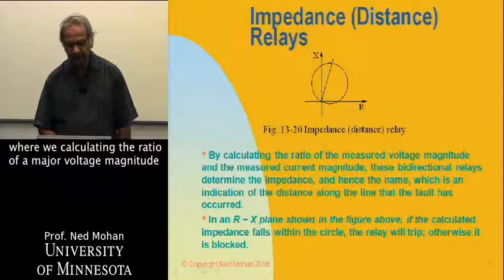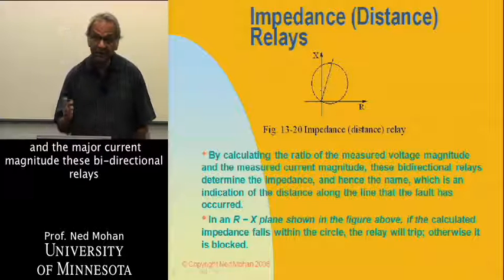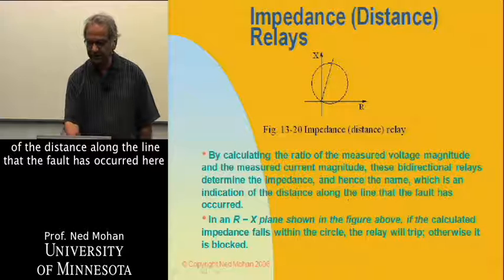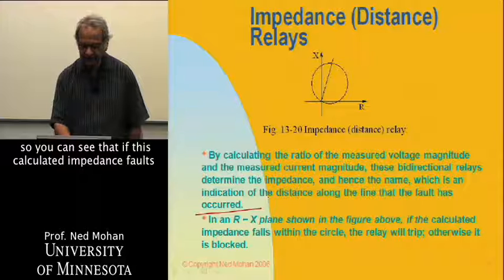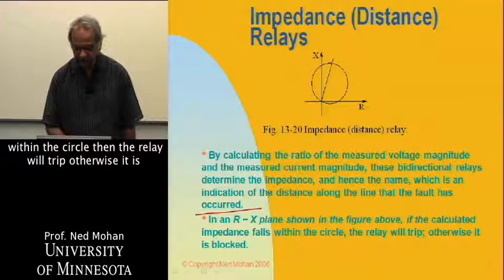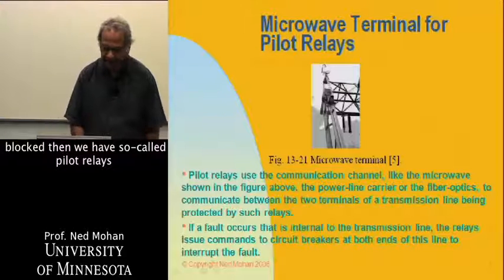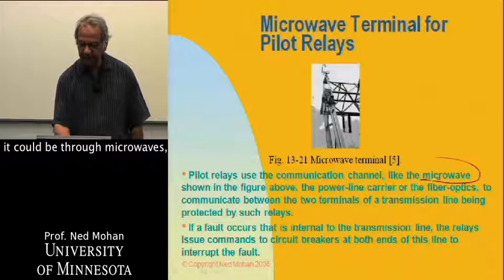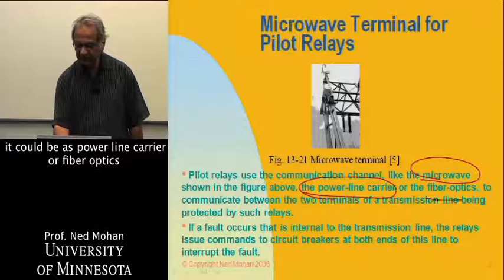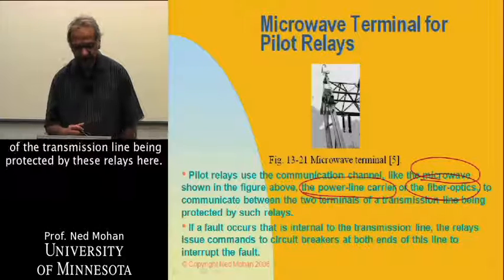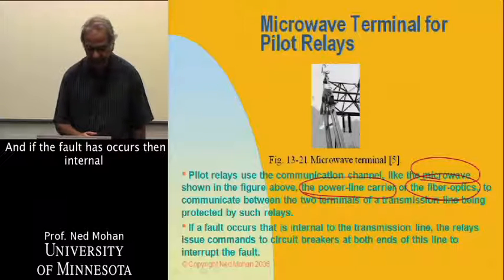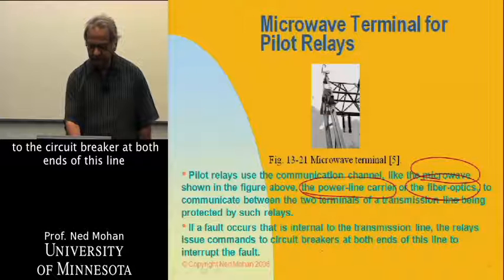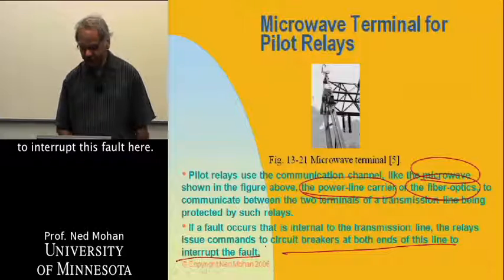Then we have impedance relays, where by calculating the ratio of the measured voltage magnitude and the measured current magnitude, these relays determine the impedance — an indication of the distance along the line where the fault has occurred. If this calculated impedance falls within the circle, the relay will trip; otherwise it is blocked. Then we have pilot relays, where there is a communication channel — it could be through microwaves, power line carrier, or fiber optics. They communicate between the two terminals of a transmission line, and if a fault is internal to the transmission line, relays issue a command to the circuit breakers at both ends to interrupt the fault.